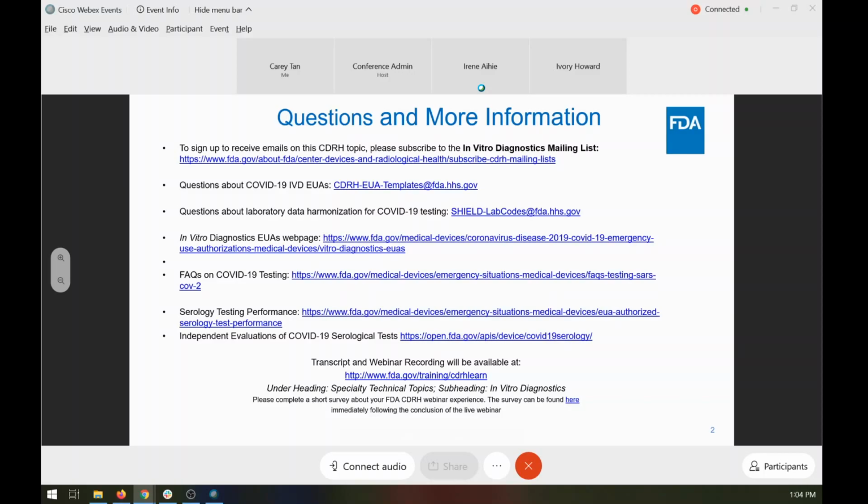If you're looking at extraction kits, for example, your test is generally authorized with specific extraction kits, and to add new ones, we would expect you to come back in. If we're using extraction kits as an example, maybe it's the same extraction kit, but there's been a small change to a buffer in that extraction kit. But the mechanism by which it works, none of that has changed. And if it were the 510K pathway, this would clearly be an internal documentation change. Sure. So that might be a specific enough question that we would want to get into the details, but I'll see if Chris wants to weigh in at all first.